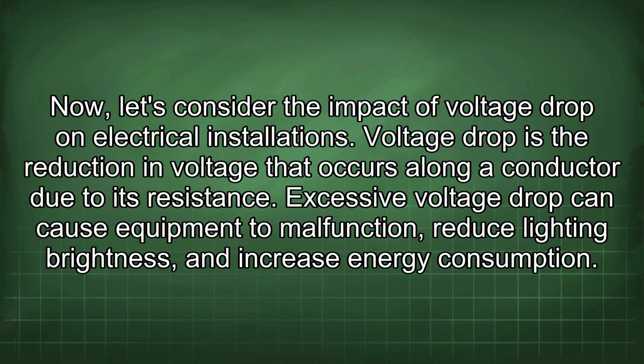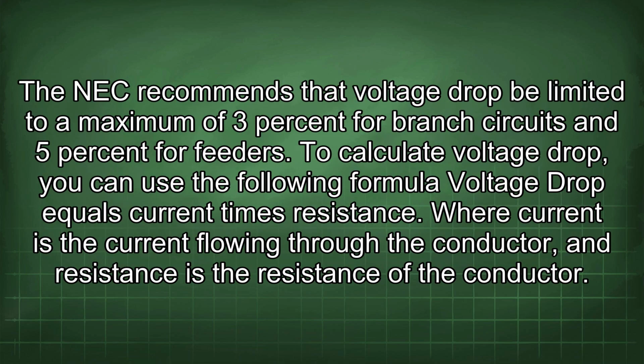Now, let's consider the impact of voltage drop on electrical installations. Voltage drop is the reduction in voltage that occurs along a conductor due to its resistance. Excessive voltage drop can cause equipment to malfunction, reduce lighting brightness, and increase energy consumption. The NEC recommends that voltage drop be limited to a maximum of 3% for branch circuits and 5% for feeders.